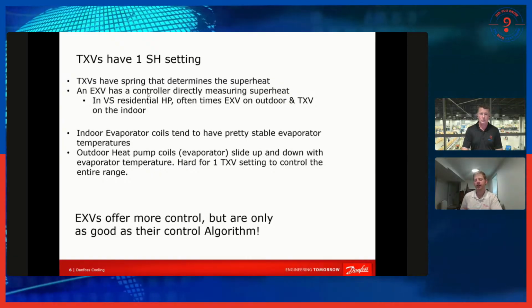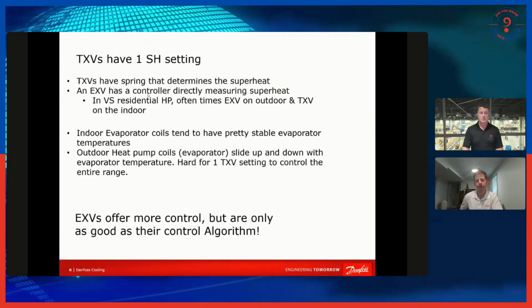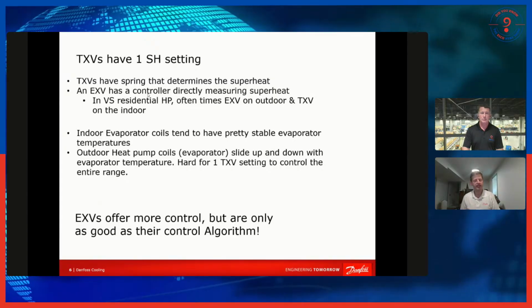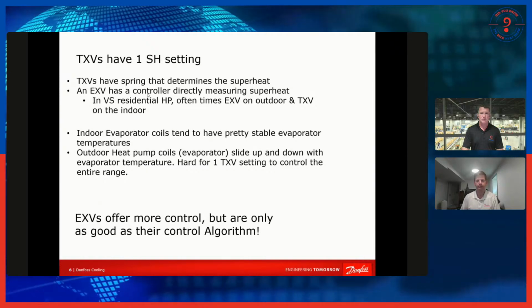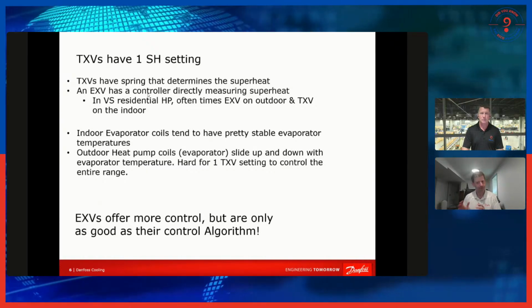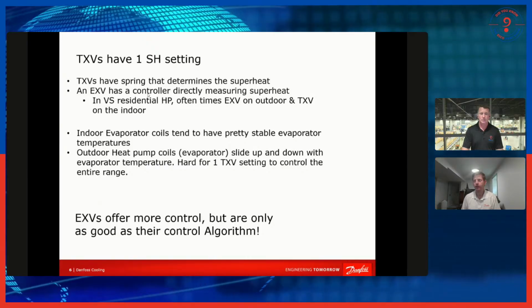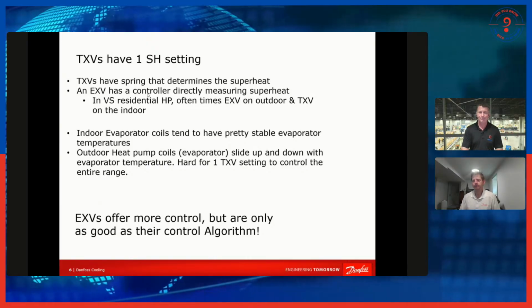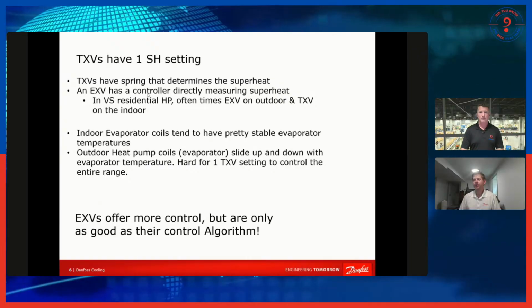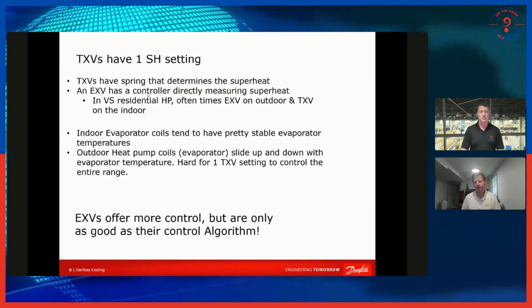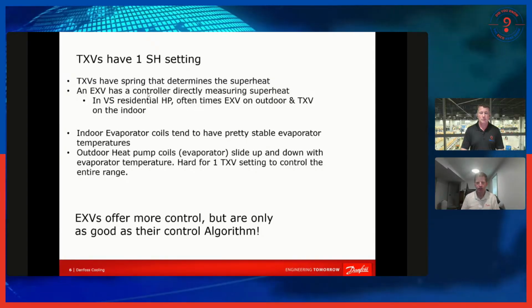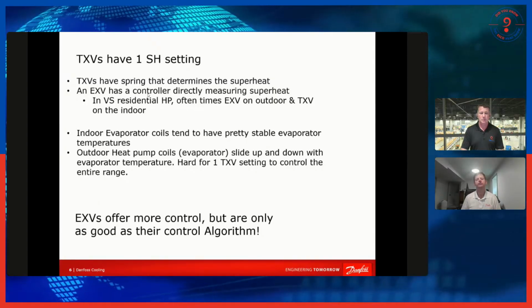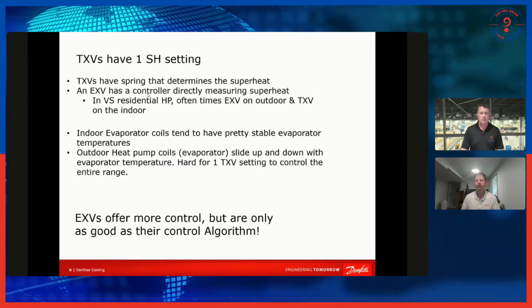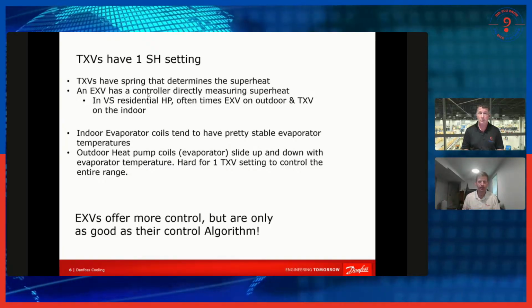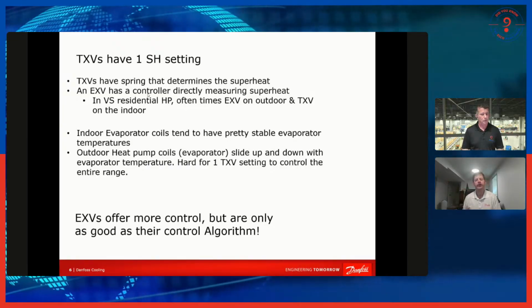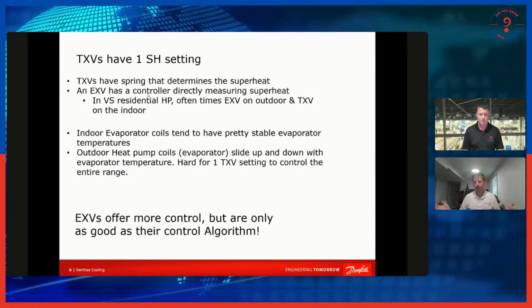And what you might find a lot of times is on residential systems, the indoor coil might still have a TXV, but that outdoor coil on the variable speed condensing unit will almost definitely have an EXV on there, because in a residential system, the indoor evaporator temperature tends to be pretty steady. Yeah, as the seasons change, if you had your gauges on there, you'd see the evaporator temperature drift around a little bit. It might go from 50 down to 45, back up, but it's a pretty narrow range. If you look at that condensing unit, that temperature moves all over the place. And then if it's a heat pump, it's really moving all over the place.